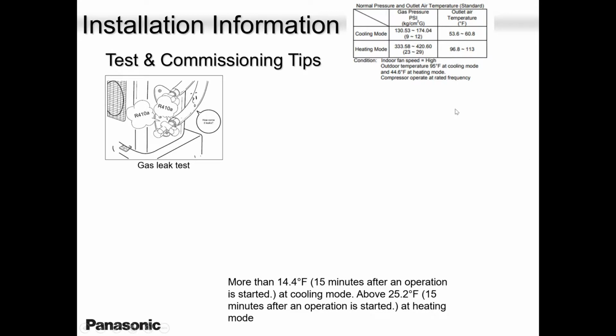In cool mode, our unit will run around 130 to 150. 170 is a bit high, but it's okay if the room is very, very hot in cool mode. But those are our ranges. If the unit is running below 120, rest assured you are low on refrigerant. So please keep in mind, our unit, unlike other manufacturers, 110 is not enough. 120 might not be enough. 125, 130, 135 is good, perfect. And in heat mode, 350 up to 425. 350 up to 425, we are good.